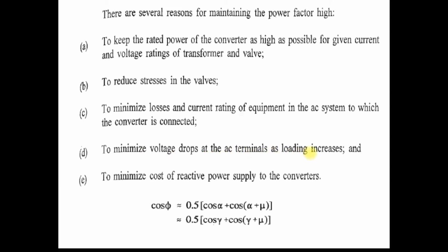Another reason is to minimize the voltage drop at the AC terminal as the loading increases. If the power factor is low, what will happen? As loading increases, more current flows, and because of that, a high voltage drop happens. So to minimize the voltage drop at the AC terminal during high loading conditions, you maintain the power factor as high as possible.